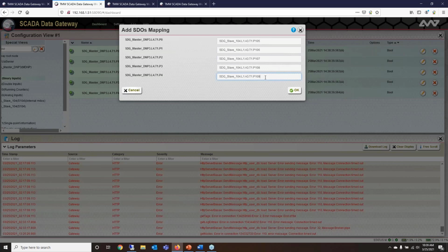If you have hundreds or even thousands of points you want to map at once, I wouldn't recommend doing it this way, as it could still be a long process. But we do have exportable configuration options in our SCADA Data Gateway. That allows you to take a CSV file over to Excel, use the built-in functions to change that CSV file, upload it back into our SCADA Data Gateway, and all those mapping points will have been done automatically.